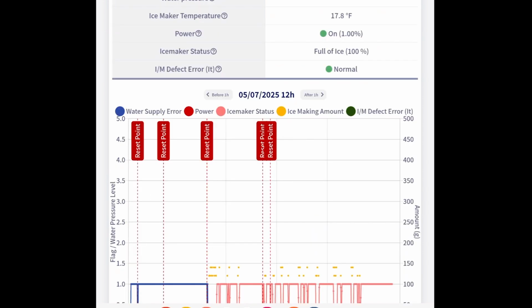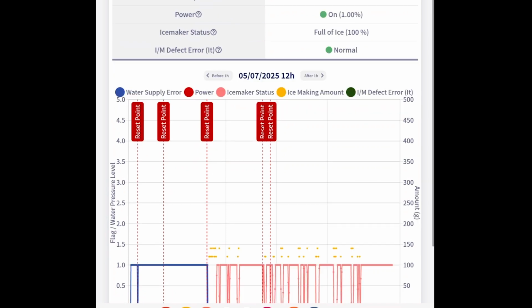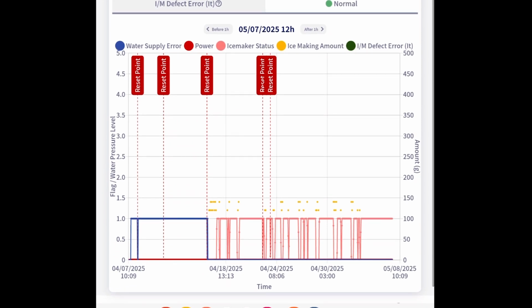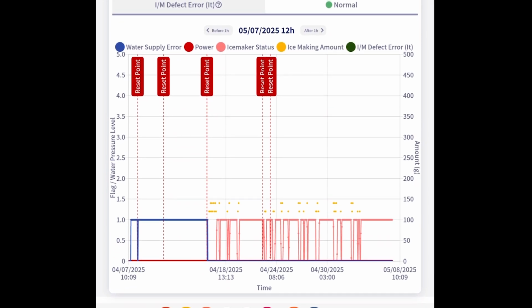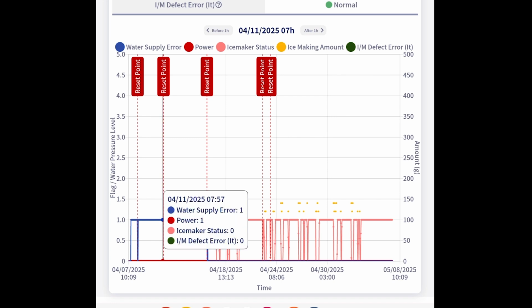More useful information that the Argus system can provide related to the ice maker is whether the unit's having any issues filling with water. So you see on the left side of our graph, we have these raised blue bars. If I click in there, that tells me that there was a water supply error, because water supply error is now showing 1. That should be 0 at all times.